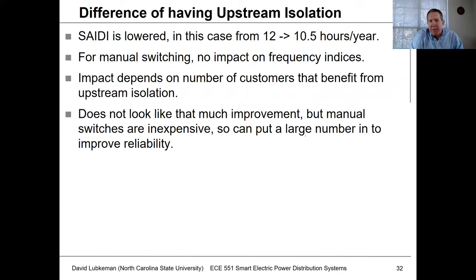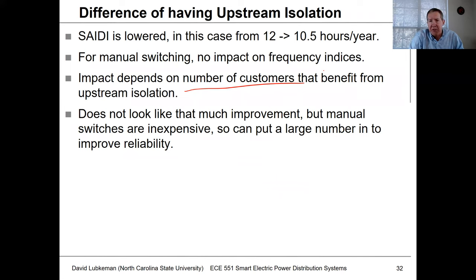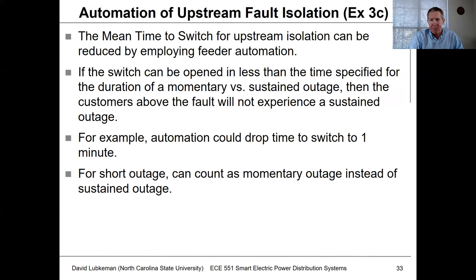This doesn't seem like that much of an impact — going from 12 to 10.5 hours per year. With manual switching, we still haven't improved the frequency index, but we have made a change on the SAIDI side. This impact depends on where customers are actually located. Even though it doesn't seem like much of an improvement, manual switches are relatively inexpensive. A manually operated switch doesn't cost much to put out in the field, so you can afford many locations compared to the cost of a recloser — it's a very economical way to improve reliability.